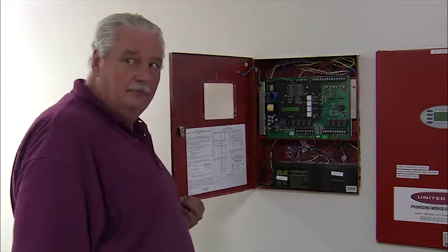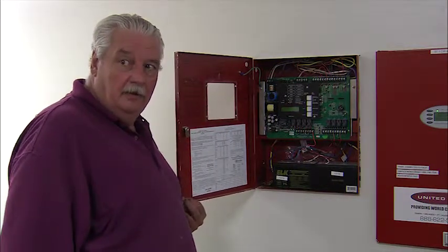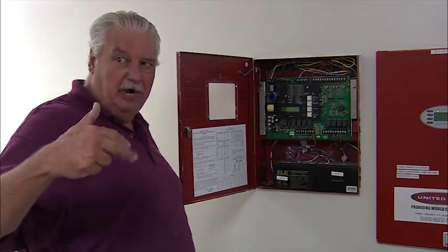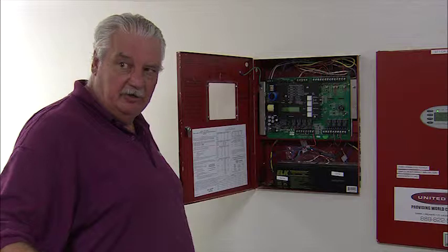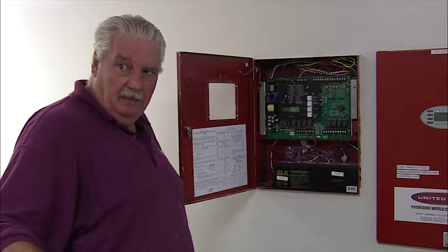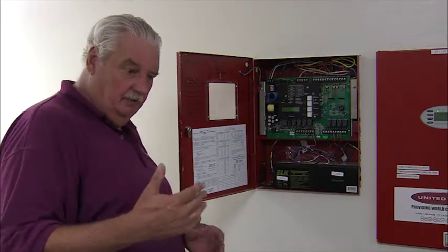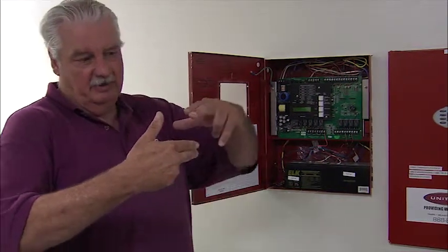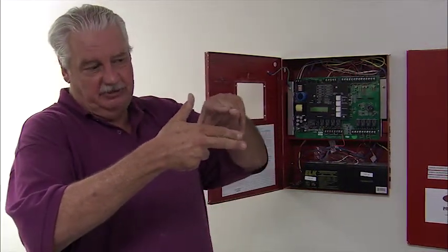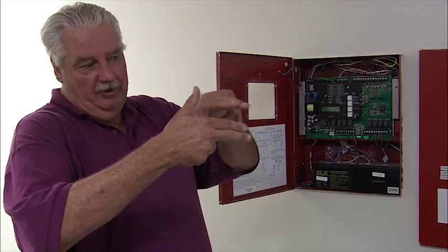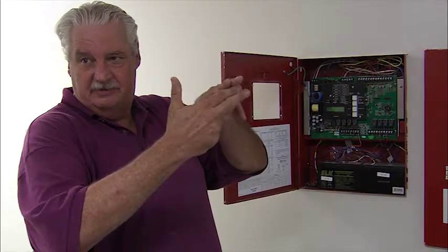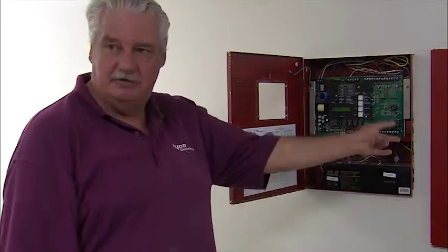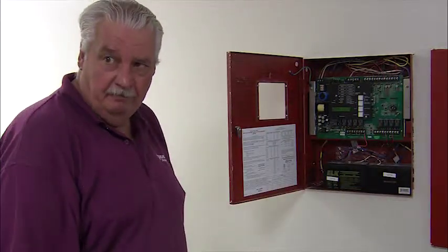And how does it know that someone has closed the valve, by a pressure sensor? Actually, on the valve, it's a micro switch, an electronic micro switch. The valve has a stem in it with a rod that pushes up against micro switches. Normally they're normally open, and as the valve closes, the arm goes up and hits the micro switch and causes the supervisory to come to this panel. Okay.